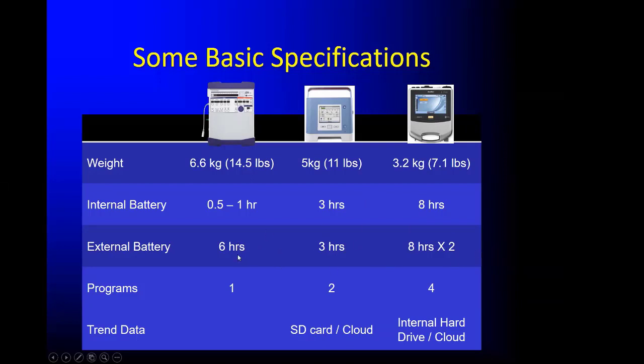have external batteries. So with routine care, the external sprint pack for the LTV can last 6 hours. There's a hot swappable battery for the Trilogy that lasts 3 hours. And then there's an external battery for the Astral that lasts 8 hours, and you can daisy chain 2 of them together. So ostensibly, you could be 24 hours away from a power source and still have ventilator function with the Astral. There's only one prescription for the LTV, which means that if you want to use a day and a night setting, the family or the nurse or the DME has to change the individual settings between those two, and that can increase your risk for error.